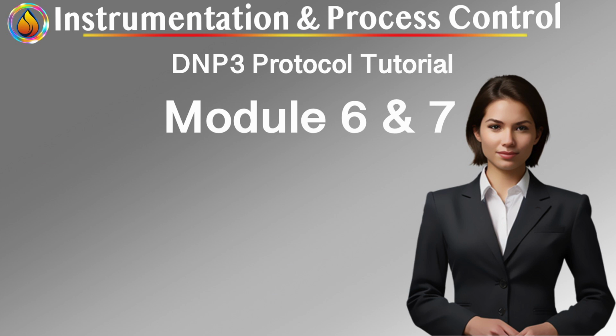Functional role of the submaster. A submaster may aggregate data from downstream devices, perform local control or automation logic, store and forward data upstream, translate or normalize data. From the upstream master's perspective, the submaster behaves like a standard outstation. Advantages: reduces upstream communication bandwidth, enables localized decision-making, improves scalability in large systems. Hierarchical designs are common in large substations and regional automation schemes.